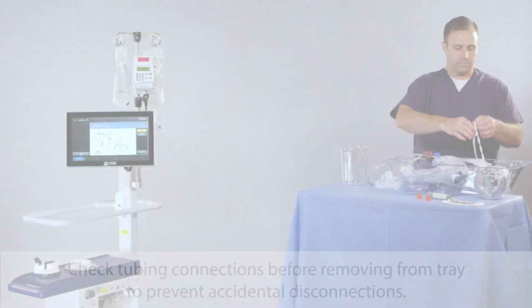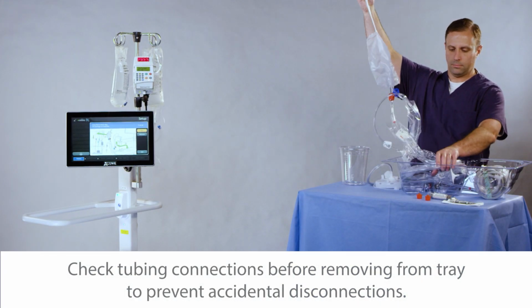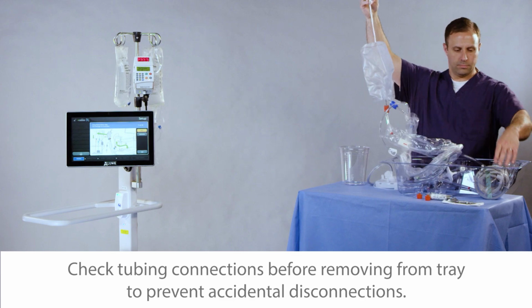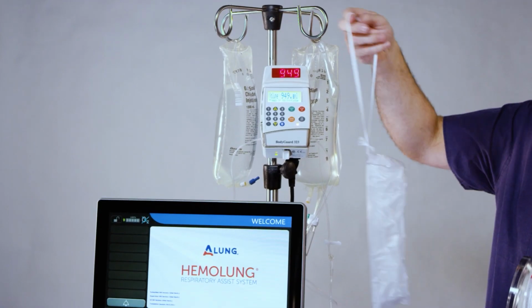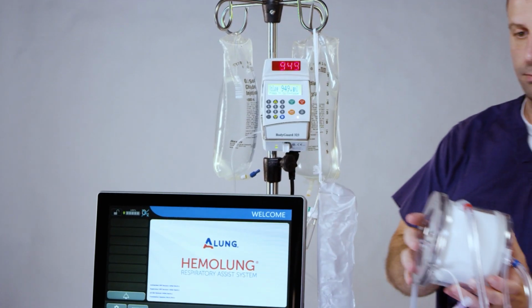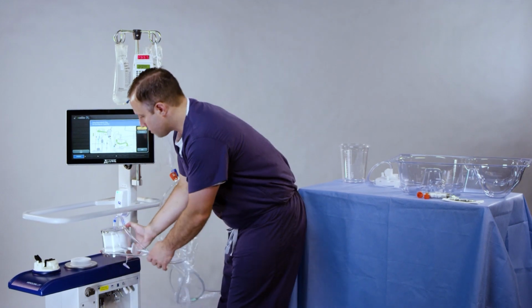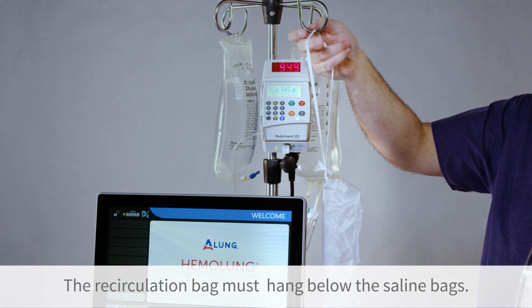Open the HEMOLUNG cartridge kit tray. Start by lifting the string on the recirculation bag to unravel the tubing, then remove the cartridge. Hang the recirculation bag and temporarily sit the cartridge on the controller. The recirculation bag must hang below the saline bags.